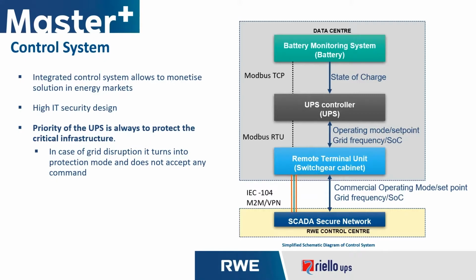However, the priority of the UPS is obviously to protect the critical infrastructure and the load, and therefore, should a grid disruption or a mains failure occur, the system will turn into protection mode and therefore it will not accept any commands from the outside.